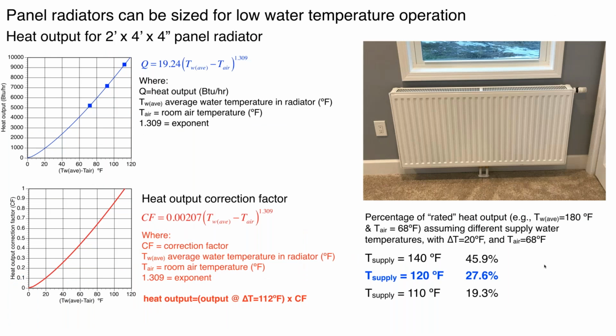Real quick, you can look at this more on the PDF file. It is important that when you size these radiators, you size them around low water temperatures. And there are correction factors over here, based on the water temperature that you want to work with, that adjust the output. Most of the manufacturers list the output at 180 degree average water temperature, well above where we want to be. But you'll see if you plot the data out here, here's a curve that basically gives you the output of a specific panel, a 2 foot by 4 foot panel with a 4-inch thickness.